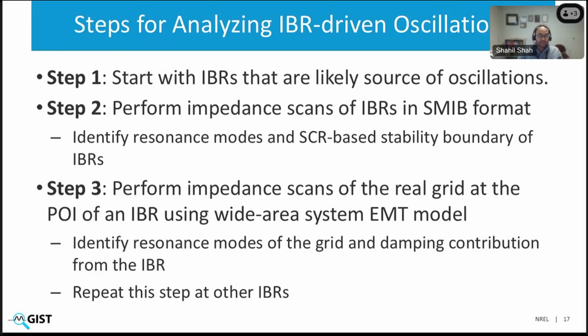So there are three main steps to do impedance-based stability analysis. In the first step, we identify IBRs which we think are the likely source of oscillations, as Nilesh described, from field measurements, particularly if you're looking at post-event diagnosis. For planning studies, we skip step 1 and just look at steps 2 and 3. Step 2 is we perform impedance scans of IBRs in single machine infinite bus format. What we really do is try to obtain those IBR puzzle pieces for different operating conditions. The goal here is to understand if those IBRs have any resonance modes. The second goal is to find whether there is any SCR, short circuit ratio based stability boundary, for example, a certain PV plant or wind plant not being able to operate stably below a certain grid strength, below an SCR of, let's say, 3.